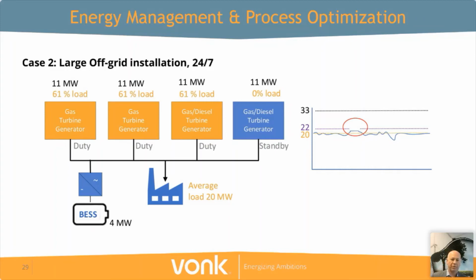That will shave off your peak, and the nice result of it is that you do not need the 3 turbines anymore, but only 2. And they will run at a higher load, therefore at a higher efficiency. This will already reduce the CO2 emissions, taking the 3rd one out of operation. Also, of course, direct CO2 emissions, energy savings. So this is a lot better situation for, in this case, a larger off-grid installation.